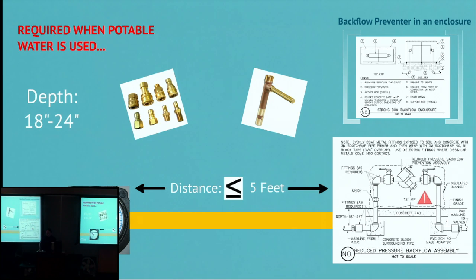And another thing to look for when you're out in the field is that the backflow has to be 12 inches above grade. And then on the backflow, there will be written the manufacturer's name and the size of the backflow. So check that it is what you've specified. And then also the backflow should have a concrete pad. It should not be just stuck into the dirt.